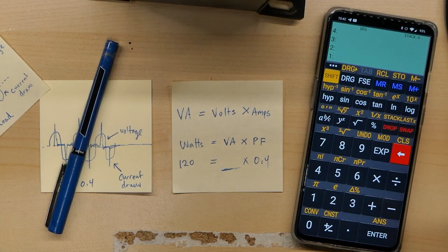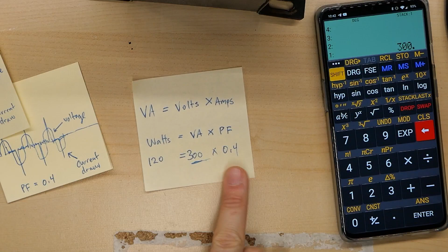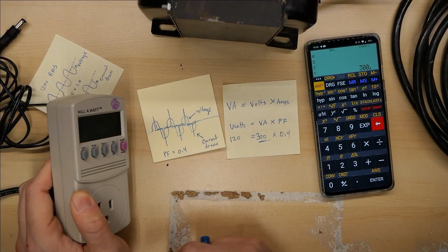Anyhow, let's quickly solve for the number of VA so we know if my theoretical power supply can work on this isolation transformer. All we have to do is divide 120 by 0.4, and that gives us 300 VA. So our crappy power supply with a bad power factor could draw up to 300 VA, which still is within the limit of this transformer, but just barely.